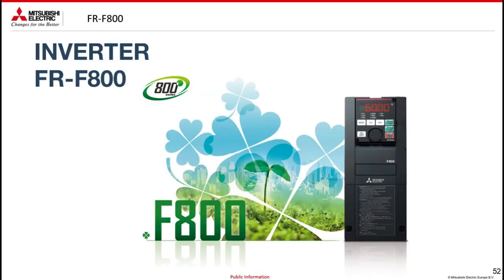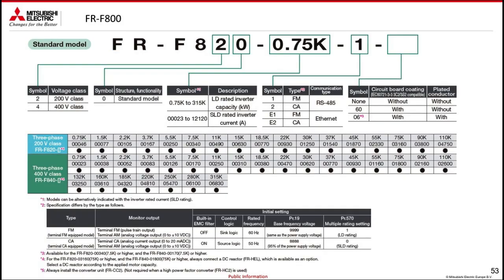Let's now talk about FR-F800, which is dedicated to pumps and fans, as it has particular functions for the latter. The code of this inverter is always read in the same way, with the difference that the European or non-European model is defined by a 1, which will be found at the bottom, and by a 2. In fact, in the case where the number 1 is present, this number is preceded by the sizes in kilowatt, whereas the number 2 is preceded by the sizes in current. It already exists in Ethernet mode by default.